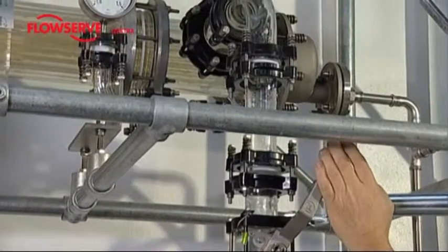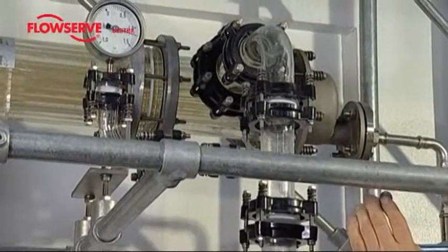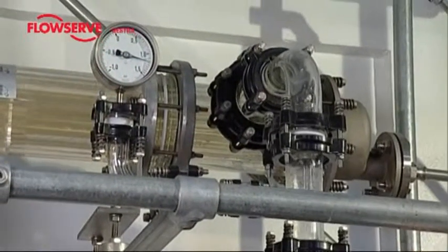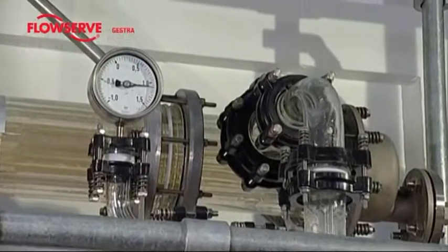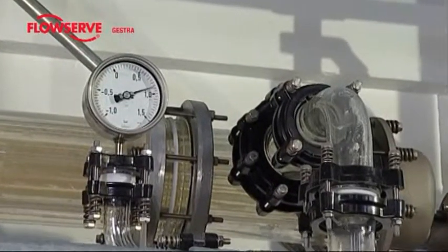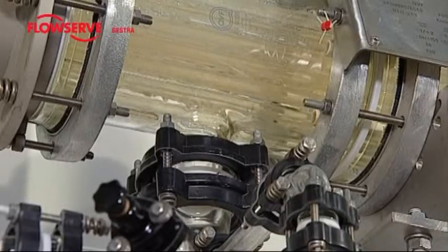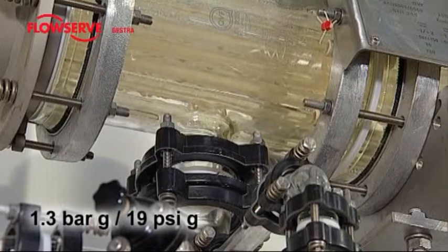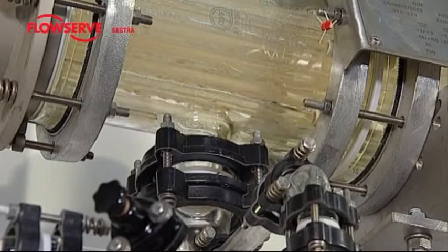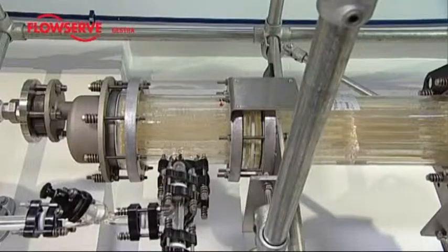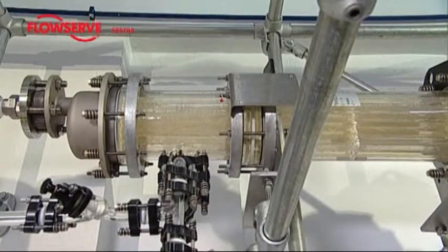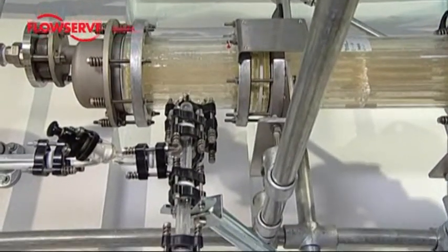Just how rapidly the pressure in a heat exchanger can drop will now be demonstrated by closing the ball valve at the steam inlet of the heat exchanger. By watching the pressure gauge at the same time, we can see how the pressure drop occurs. When the operating pressure is increased again to 1.3 bar G, the float trap drains the heat exchanger immediately without banking up. It's absolutely essential to ensure drainage without any banking up for horizontal heat exchangers.